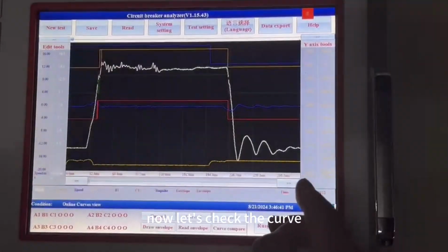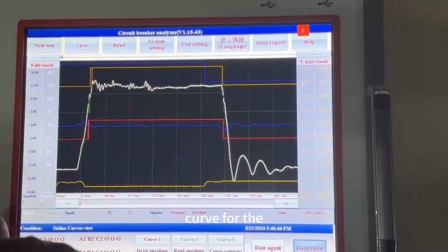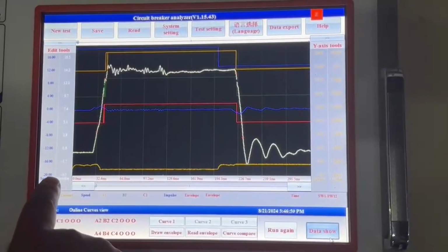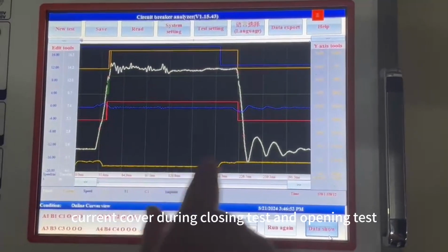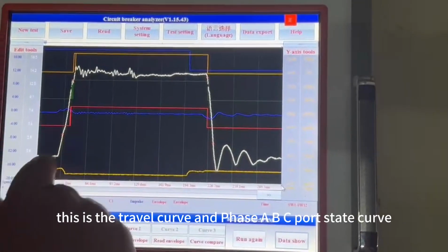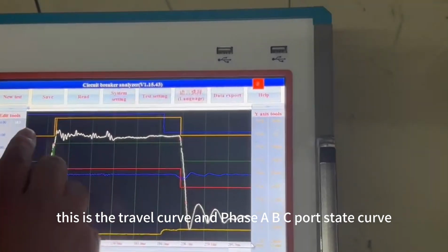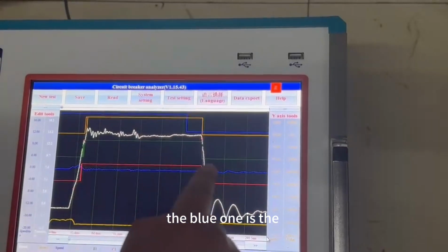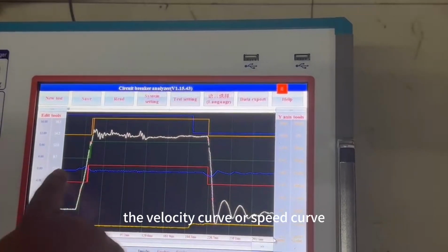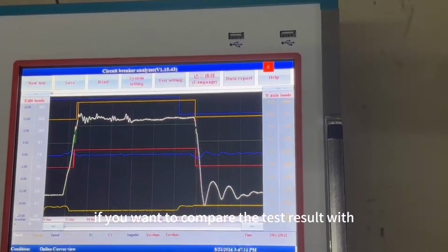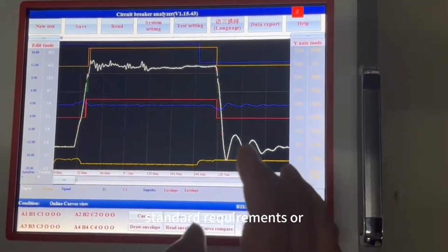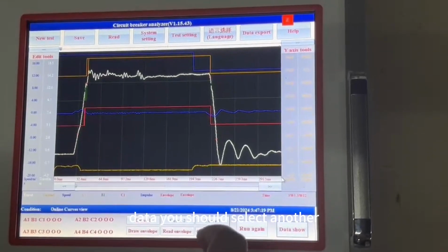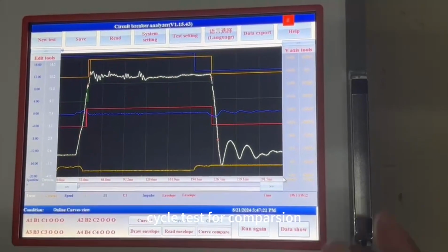Now let's check the curves. We can see this is the curve for the CO tester. Here is the current curve during the closing test and opening test. This is the travel curve, and the phase A, B, C port state curve. The blue one is the velocity curve or speed curve. If you want to compare the test result with the standard requirements or the historical saved test data, you should select another circuit tester for comparison.